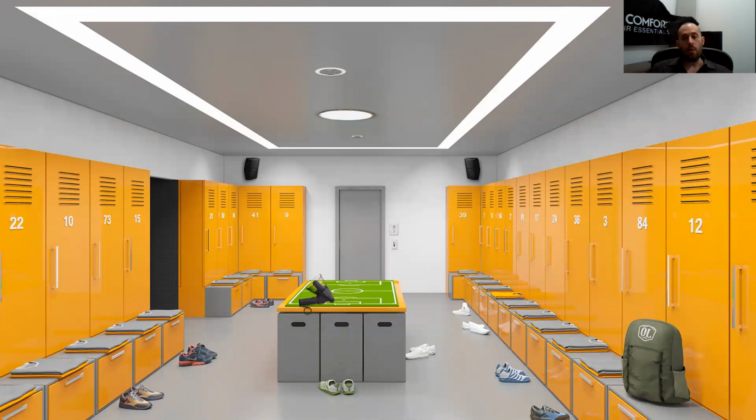Locker rooms. Now, we usually get this call to get rid of the odor, but this was that they kept having outbreaks of MRSA. And MRSA is that staph infection on steroids. Bad news. Now here, we needed more fresh air, but it turns out they had plenty of fresh air.